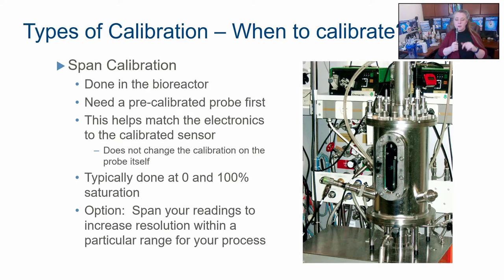Polarographic probes that you cannot pre-calibrate here, you might calibrate and write down your numbers later or earlier, what your voltages were. When you get to the bioreactor, it may ask you to input that data and then you still do a span and that does everything. Or you may just do a span calibration in polarographic probes. Okay. Any questions on that? Perfect. Yeah.